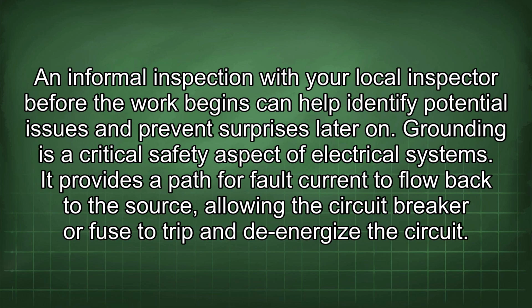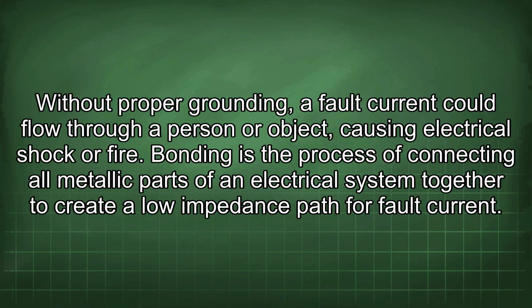Grounding is a critical safety aspect of electrical systems. It provides a path for fault current to flow back to the source, allowing the circuit breaker or fuse to trip and de-energize the circuit. Without proper grounding, a fault current could flow through a person or object, causing electrical shock or fire.